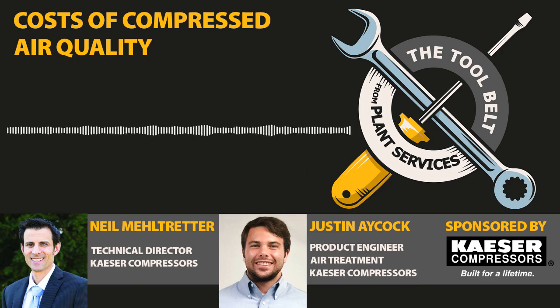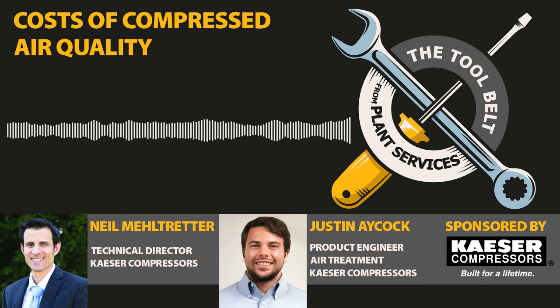The neat thing that you can do these days is if you have a master controller, which has all your pieces of equipment, all your compressors on really one pressure setting. So most people say, oh, it's a glorified pressure gauge. Well, that's true. Really, you can see, it's 98 pounds right now, 98.3. Oh, it's 97. What's going on? But it gives you an opportunity to drop that pressure 1 psi at a time. So what we usually tell operators is once that master controller is in, start dialing that pressure down 1 or 2 psi a week, and then see what happens.